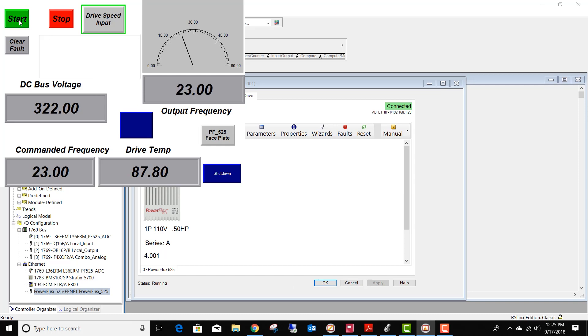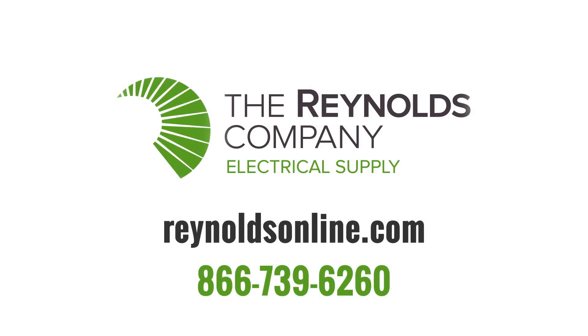We can start our drive, see a commanded frequency, and it is in fact running. This takes about 45 seconds. So in about 45 seconds, we've replaced the drive, made all the connections, and we've used no laptops. We've had no configuration files. We haven't had to call anybody within maintenance. We simply replace the drive, and it works. I want to thank you for watching this video. If you would like more information, please don't hesitate to contact us or check out our website.